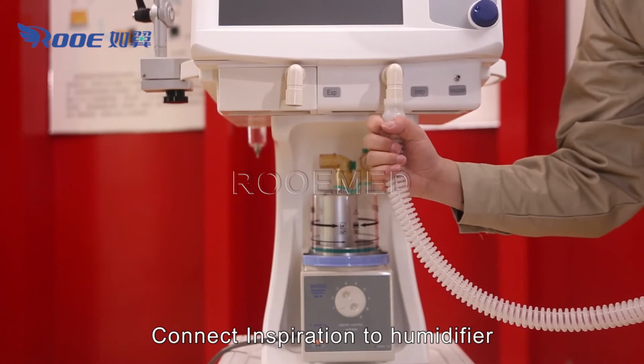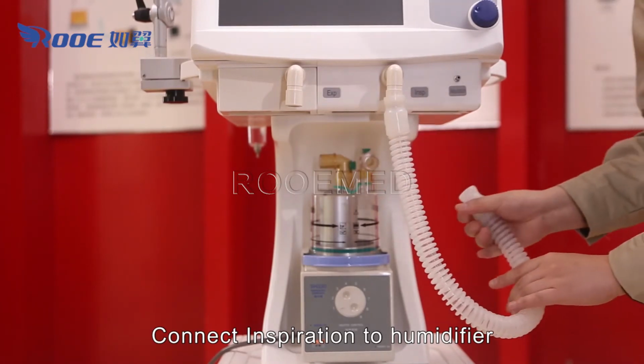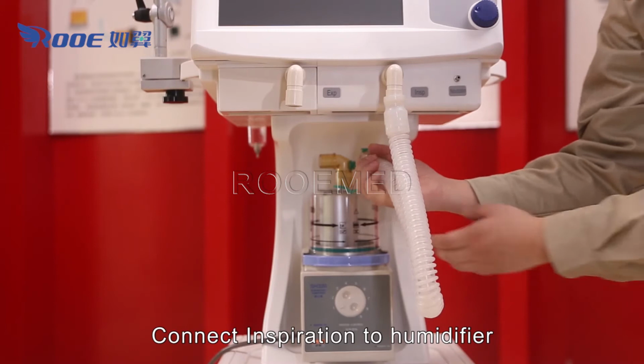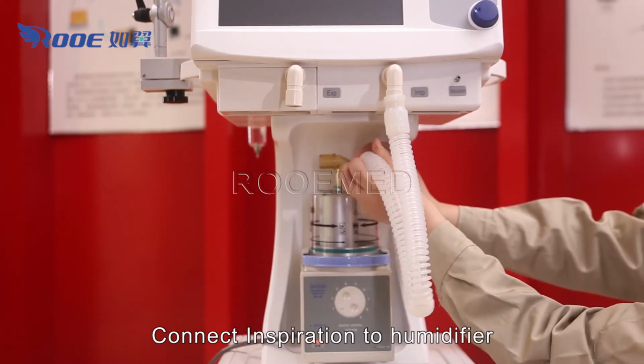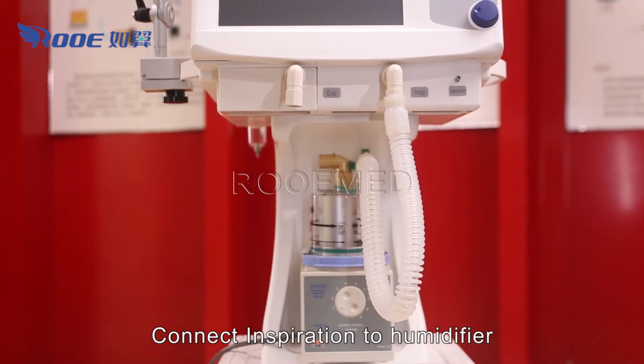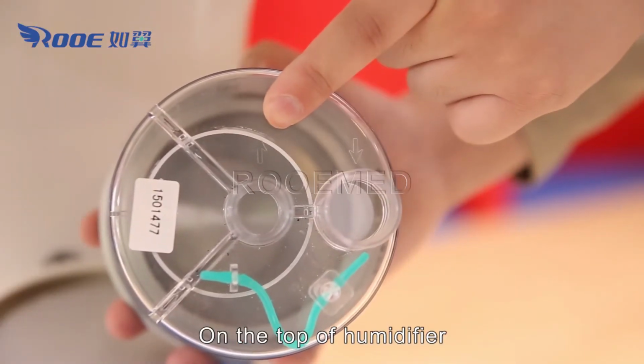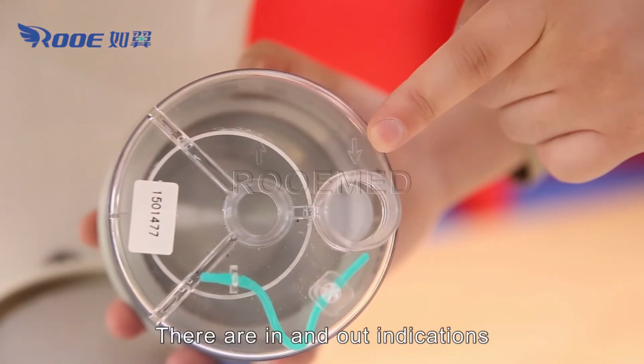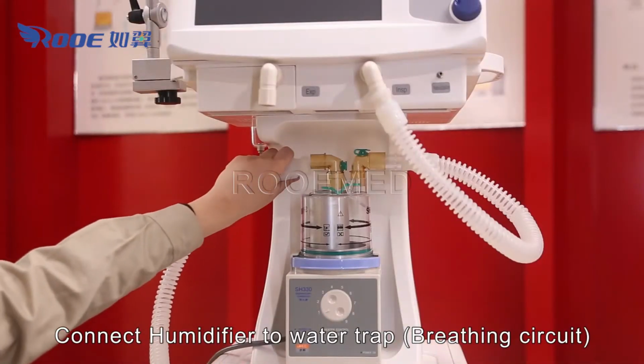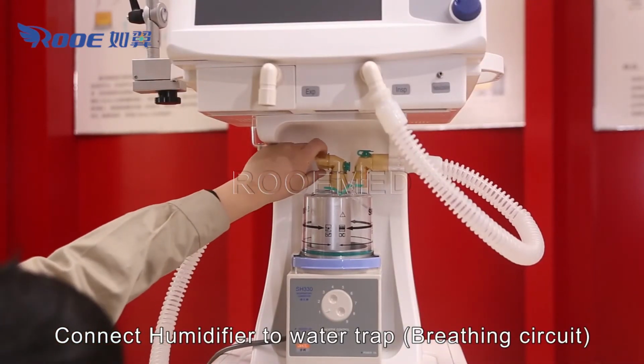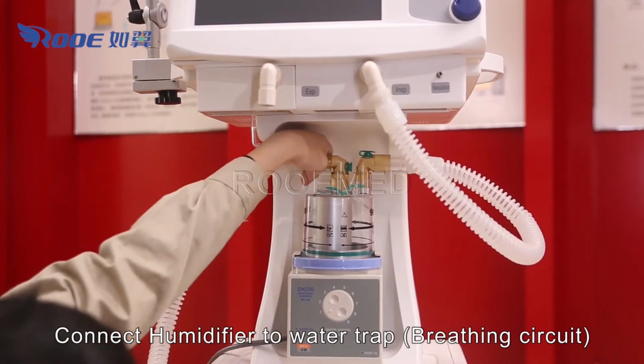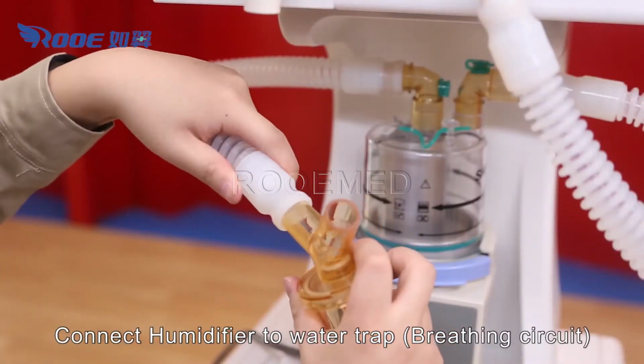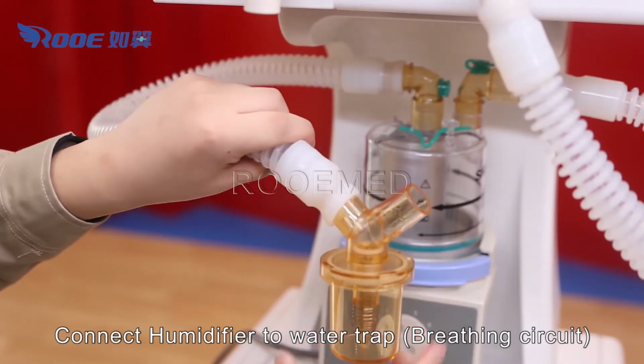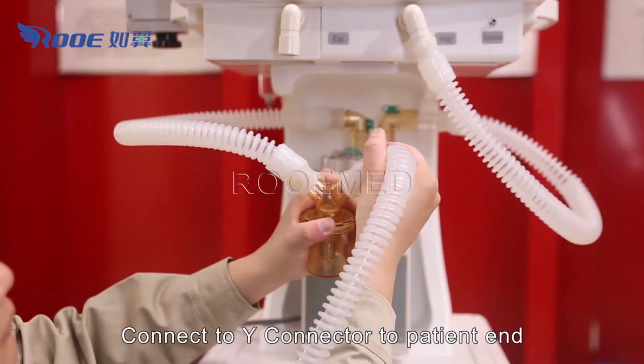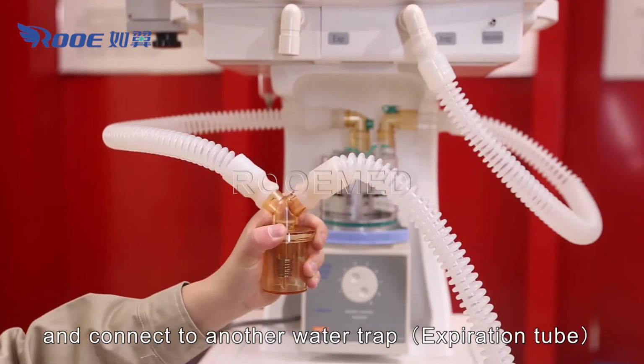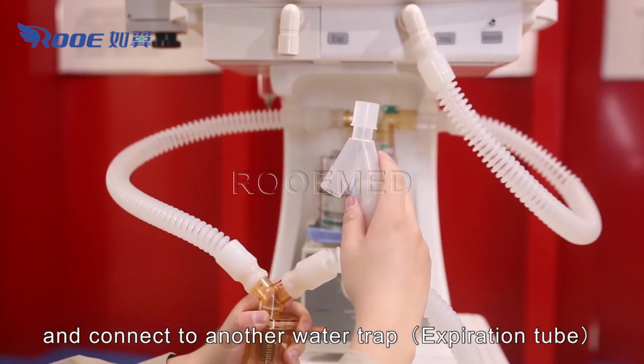Connect the inspiration tube to the humidifier. On the top of the humidifier, there are in and out indications. Connect the humidifier to the water trap and breathing circuit. Connect the Y connector to the patient and connect to another water trap. Expiration tube.